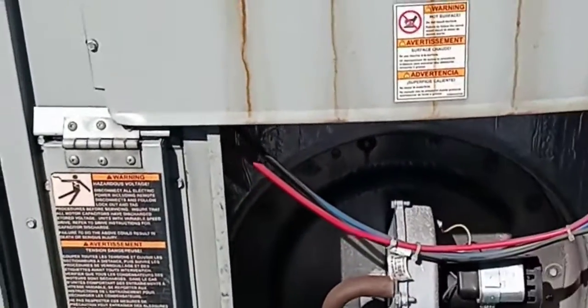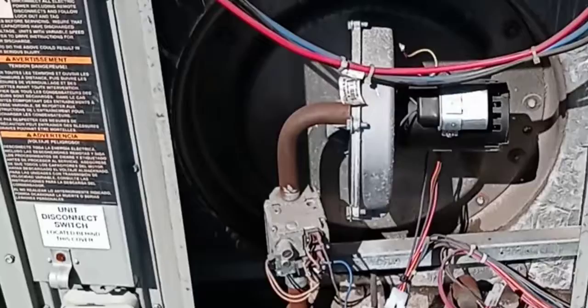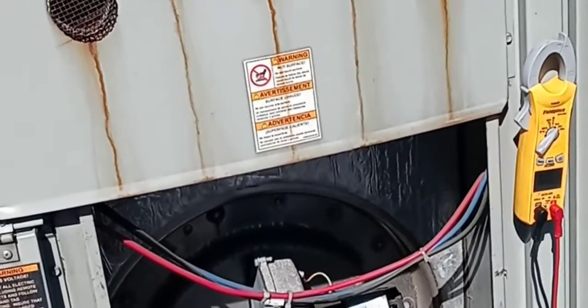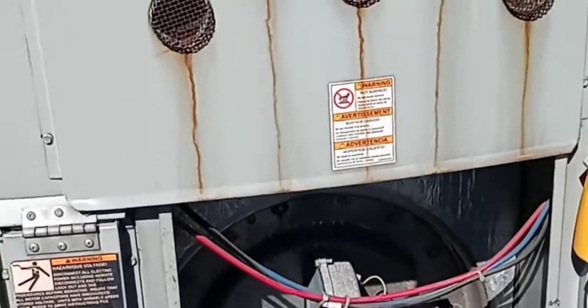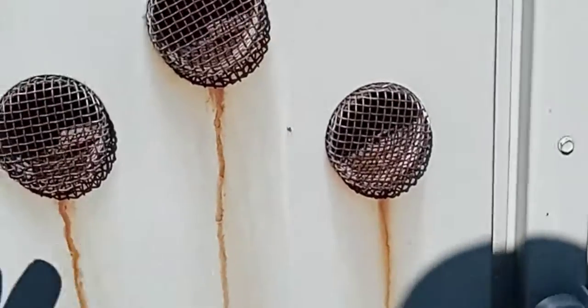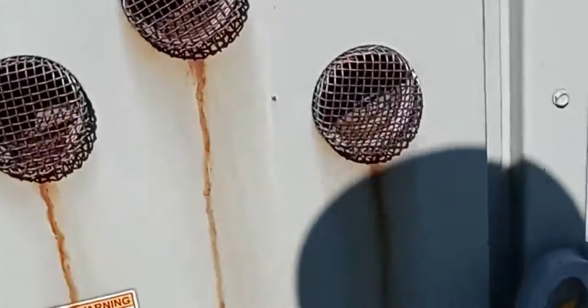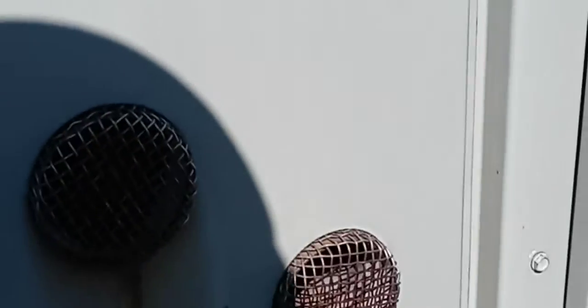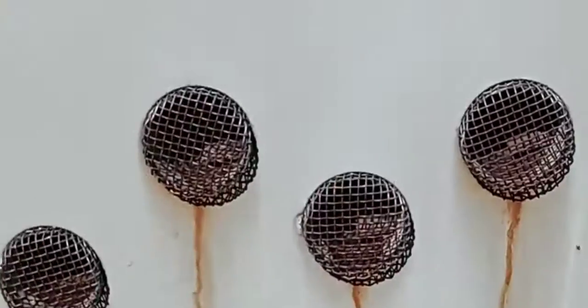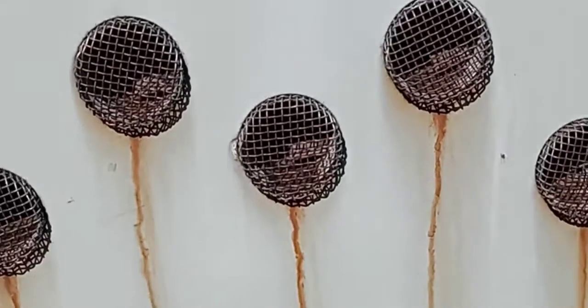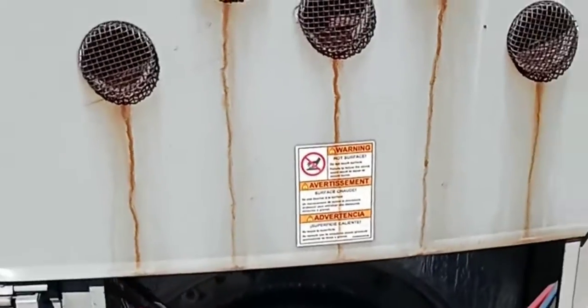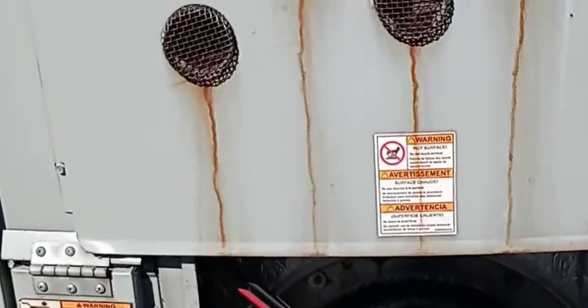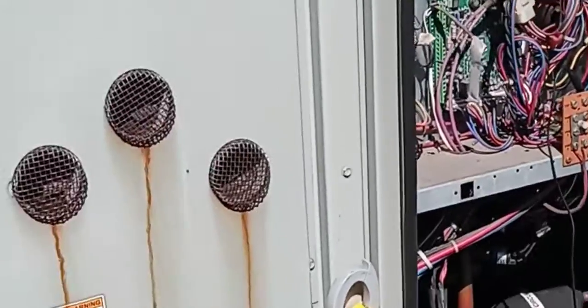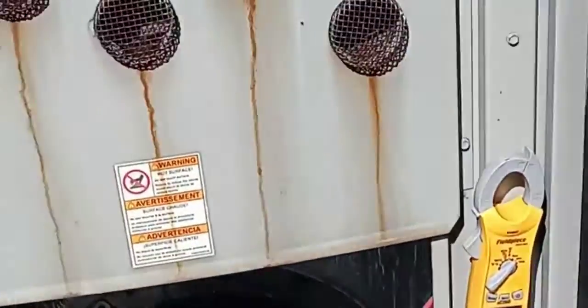But then when I came to the heat, I noticed the heat was stuttering. My inducer fan came on, but if you guys know anything about heat, the inducer fan will come on, and then when the actual heat kicks on, it'll sound like the unit's coughing. It'll make a coughing noise, in the machine world, basically, to paraphrase it. So I noticed that, I reset it a couple of times. I tried to do a test mode about 2 or 3 times. And then that's when I said, okay, I got to take this panel off and start investigating a little bit more.